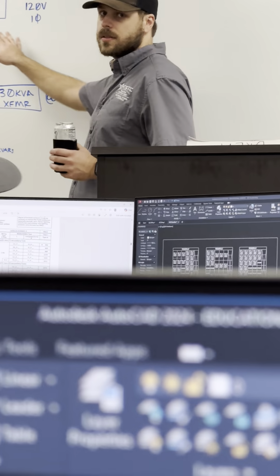Anybody have any questions on how to size that MCC transformer? So you're only gonna have one of those, right? You're gonna have 6 of those, and they're all gonna be 30? Right. Okay. Yep. So each MCC is sharing those loader receptacles, each MCC is gonna have to have a transformer, a panel, and then the receptacles that it's serving. Everybody's good with that sizing?